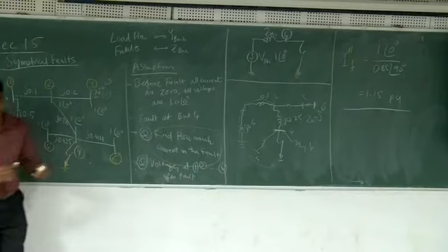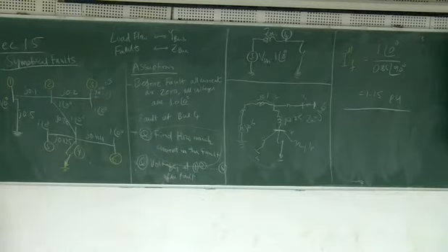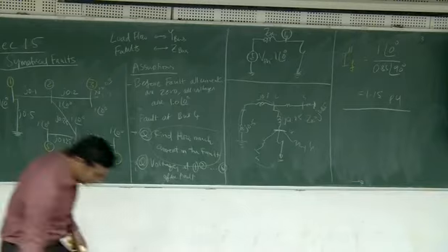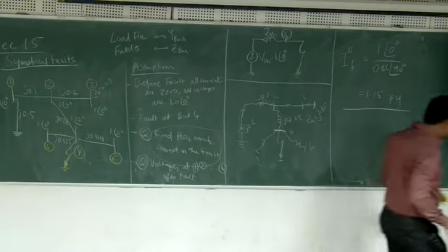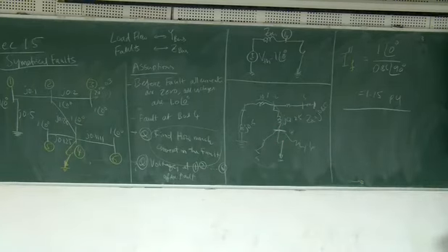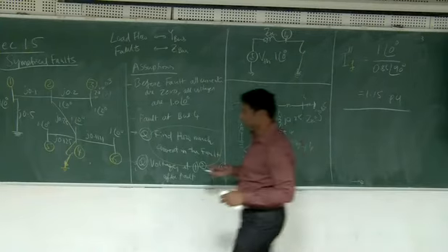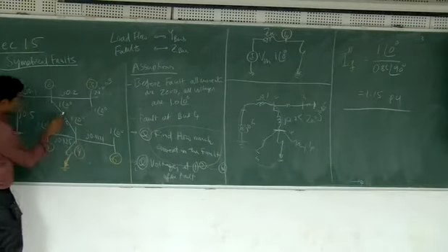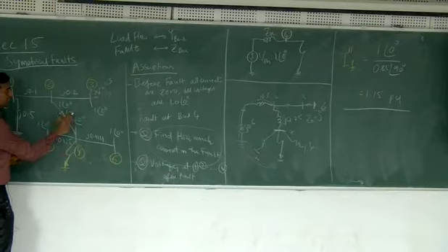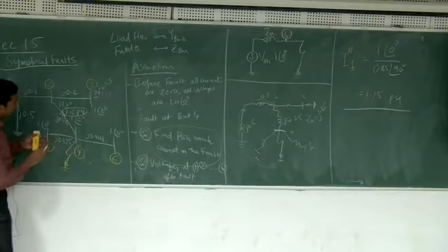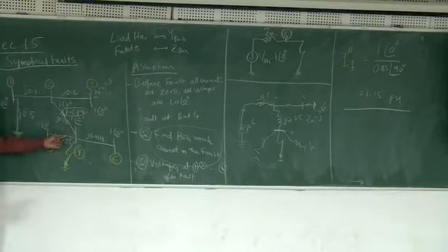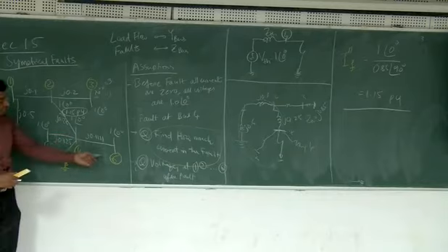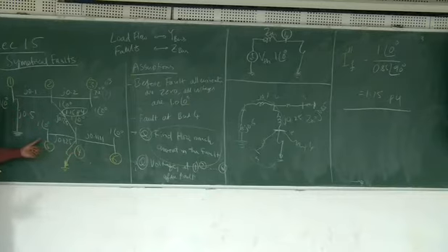Okay. After the fault is over, what are the bus voltages? Like during the fault. So how will you calculate that? Just look at this current. That 1.15 current is flowing from 2 to 4. Current from 4 to 5 is 0. Current from 4 to 6 is also 0. So therefore, voltage at 5, voltage at 4, voltage at 6 are all equal.